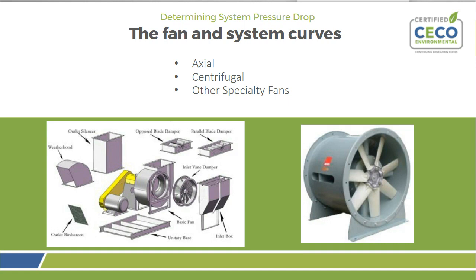When you have just an elbow without the proper amount of straight duct, you can overload the fan wheel, which can cause fan damage. You can also have an inlet damper on the fan or an outlet damper. And the unitary base is a nice solid base where you can plant the fan housing, the pedestal, and the drive. And there are other fans out there that are generally hybrids of an axial or centrifugal design.